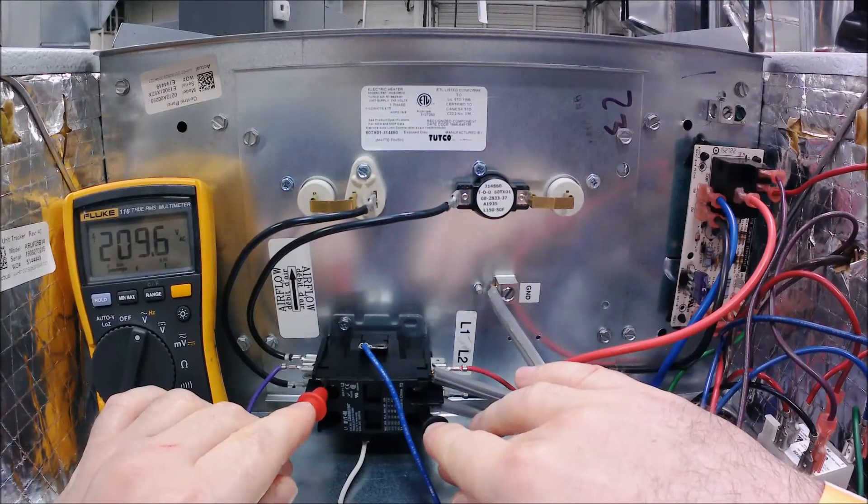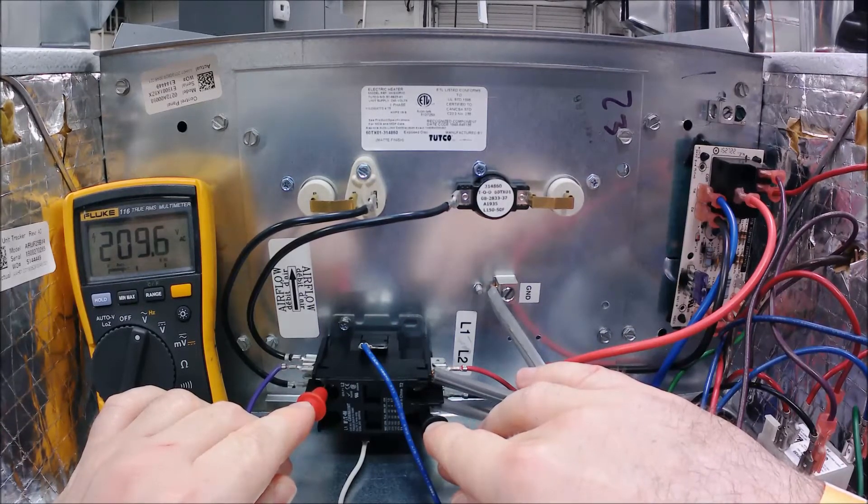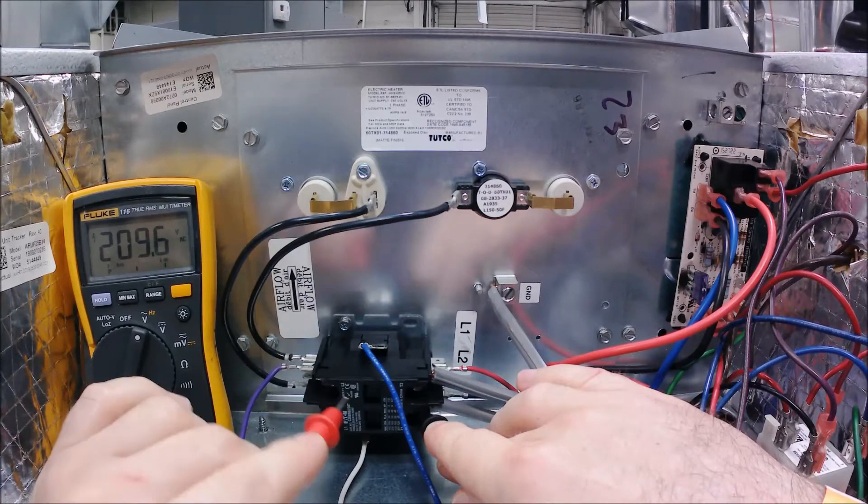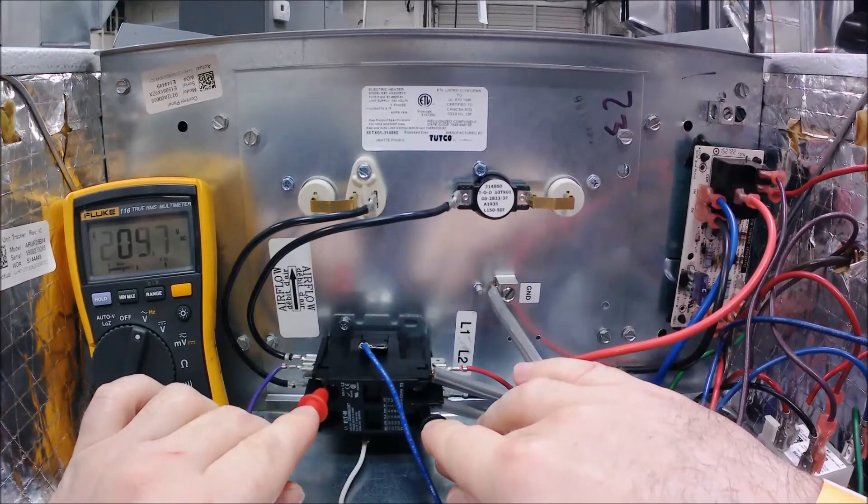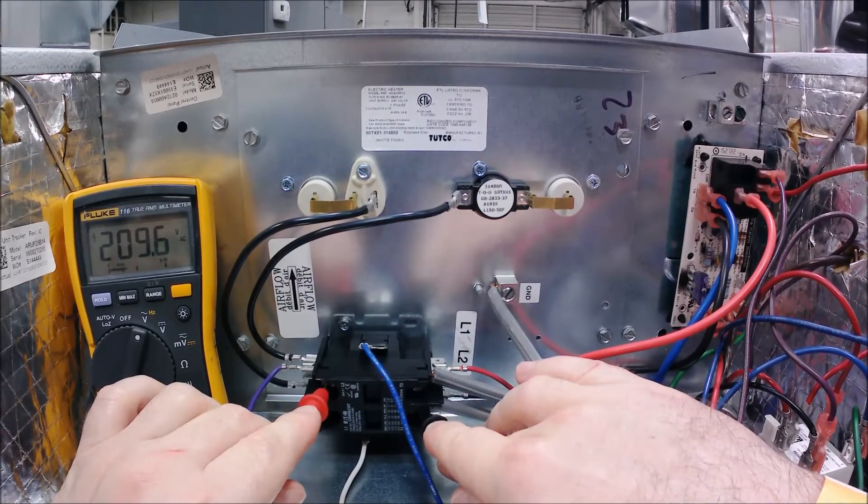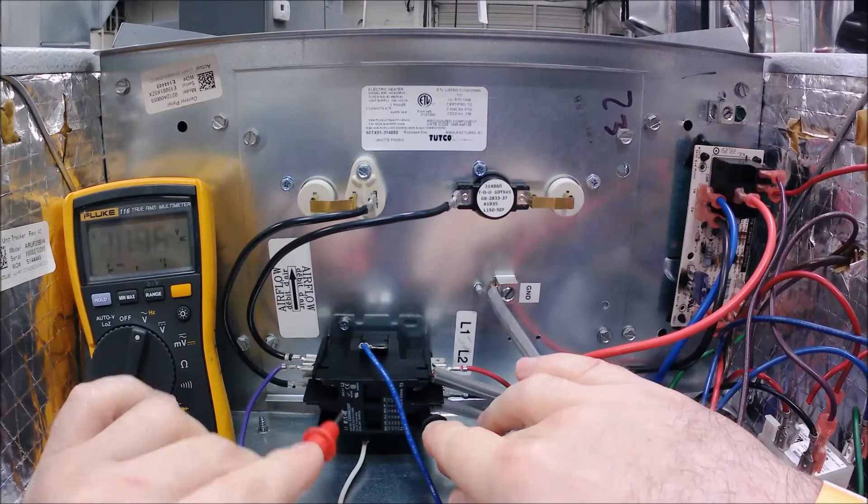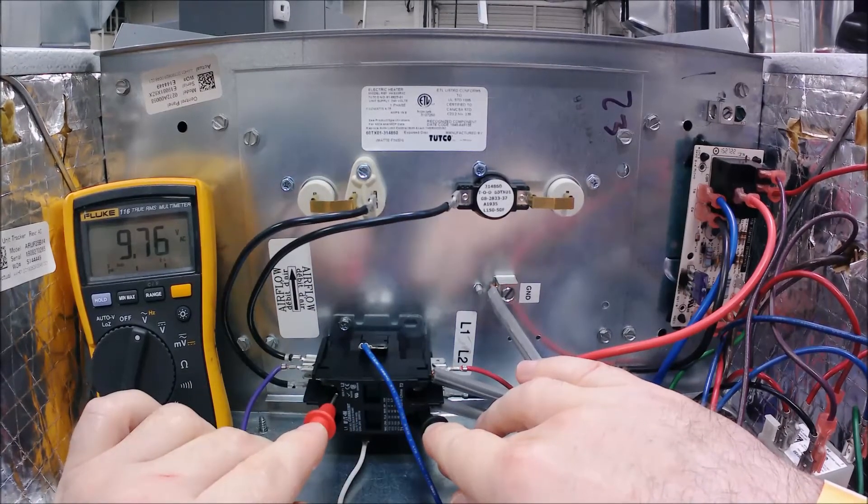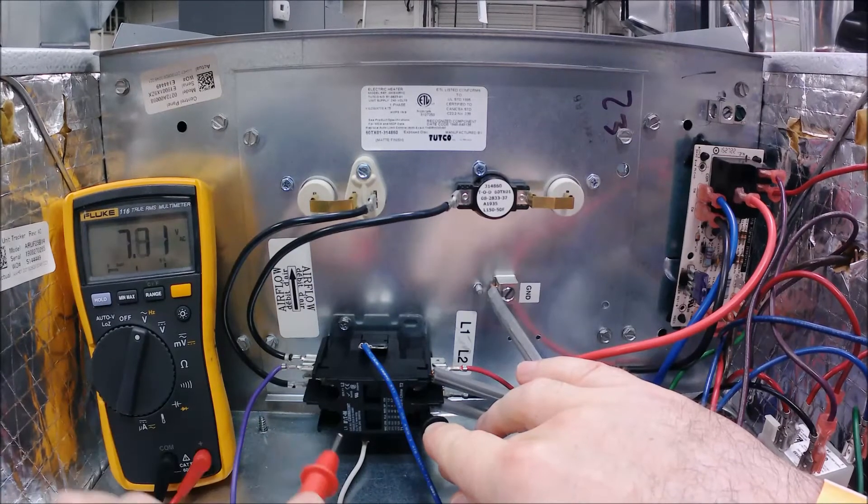And I should get 210 - if the contactor switch is closed, then it should pass all power. So you can see here that I did get that reading. If you're ever in a situation where you got zero, if you have power going in the switch and not power passing through, you know it's safe to say that switch is bad.